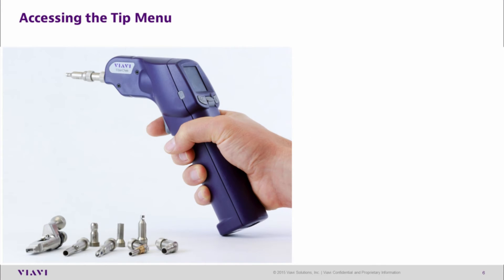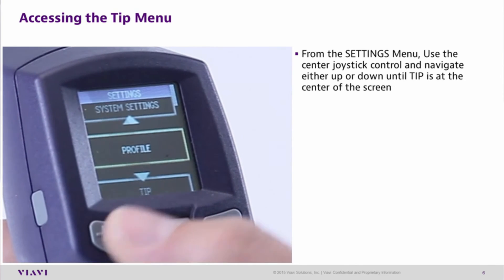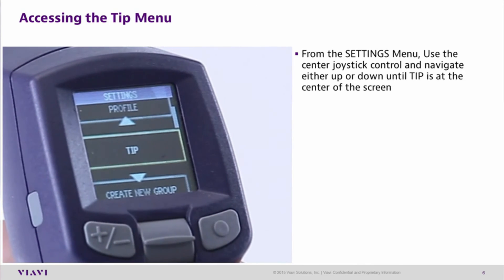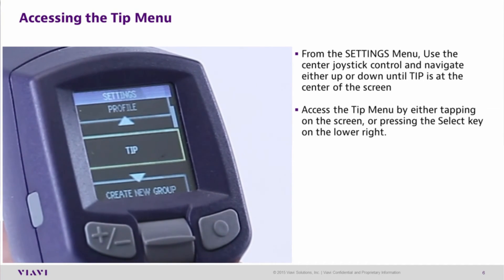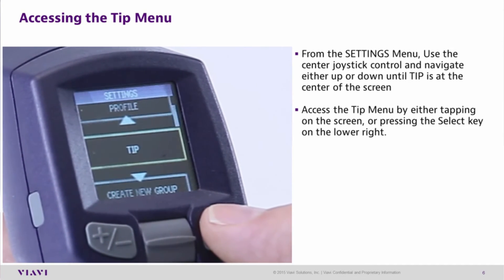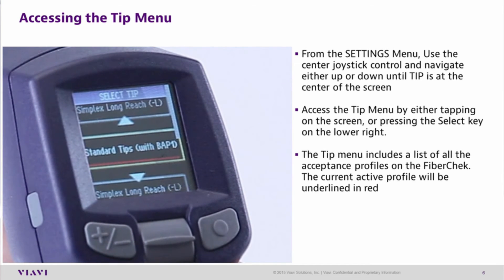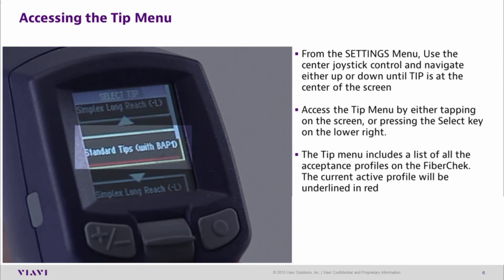Accessing the tips menu. The tip settings allows the user to select the best optical settings for the type of inspection tip that's currently attached to their probe. From the settings menu, use the joystick to navigate up or down until tip is at the center of the screen. Access the tip menu by tapping the screen or pressing the select key in the lower right. The tip menu includes a list of all acceptance profiles currently loaded on your FiberChek probe. The current selected tip will be underlined in red.